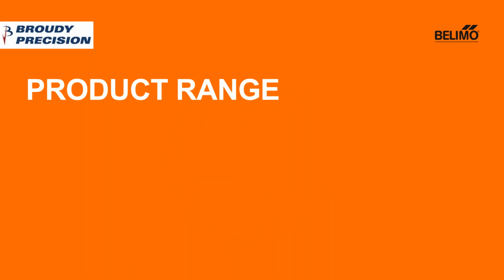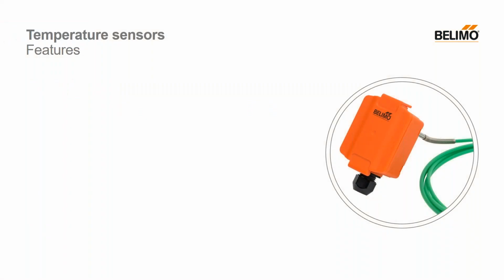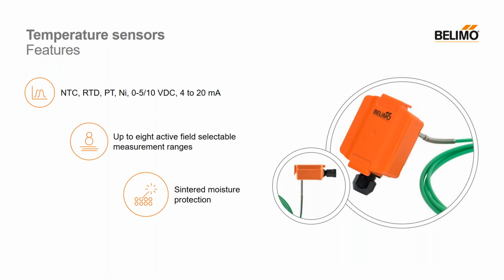So what we're going to do now is dive down and take a look at the product range itself. We're going to break it down by temperature, humidity, and things like that. And of course, the first thing we're going to look at is temp sensors, because they're probably the most common sensors you use on a job. As I mentioned, the sensors have all the standard NTC, RTD, platinum, nickel outputs. Our active sensors are configurable with 8 ranges, so you can configure them from 0 to 10, 5 to 10, 4 to 20, 0 to 20, and other ranges like that.